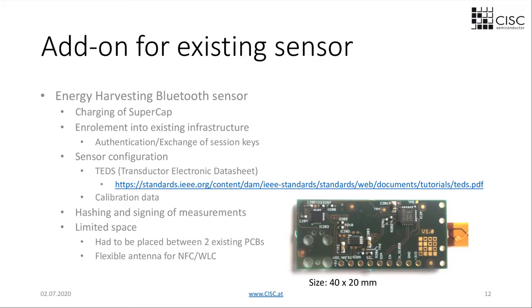So what was it used for? Basically, the sensor itself is a very generic sensor, so you can connect, for example, a temperature probe or a pressure probe or something else on it. The sensor itself does not know what he is doing at the moment, so there needs to be functionality to tell the sensor what kind of sensor it is, what is the accuracy, how is the calibration data, and things like this. We had the NFC link, and we can tell the sensor using so-called TEDs, these are transducer electronic data sheets, what kind of sensor it is, like a temperature sensor with a specific accuracy, and also give the sensor information about its calibration or about the calibration of the probe connected to it.